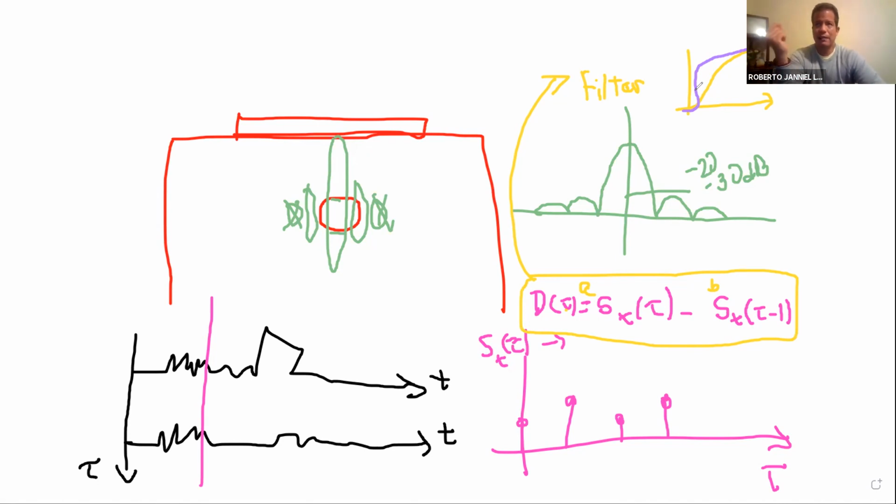That is an answer that probably doesn't satisfy your question, in the sense that, sure, I understand why it cannot be mega long, but still, how long can it be? It's still a tough question to answer. I can tell you that in practice, ultrasound systems that work with conventional imaging configurations, based on focused beams and so on, typically have ensemble sizes. Your ensemble is your collection of firings, right? So your ensemble size, meaning how many firings you have in your ensemble, would typically range between 5 and maybe 11 or 16.